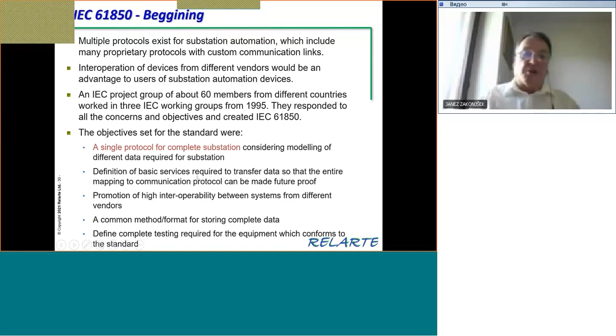There was also testing and so on, which we can see a little better in this picture. Everything was included here: system configuration was defined, the structure for protection and control, how it should go, especially communication between bay devices. Fault records were established still in COMTRADE format, and time synchronization for all of them.